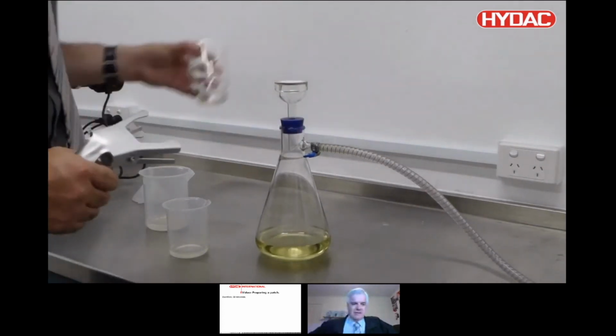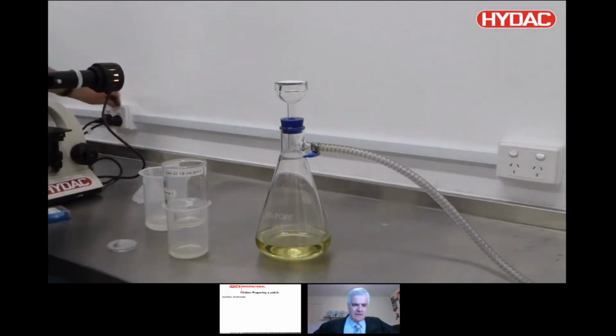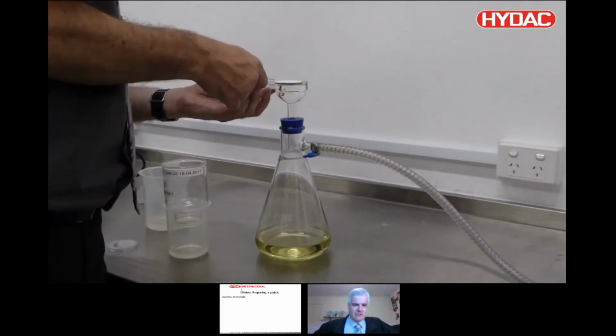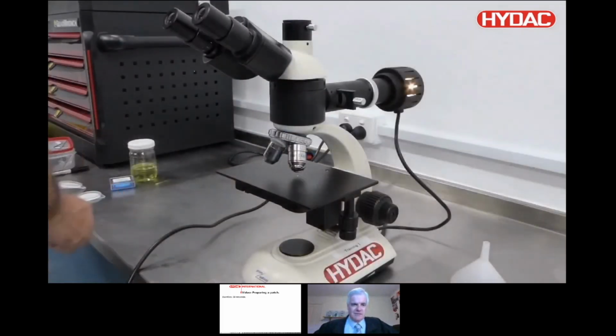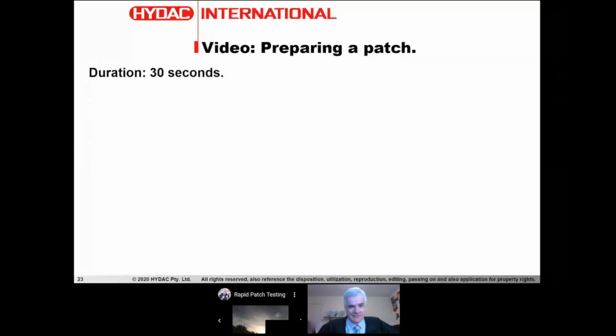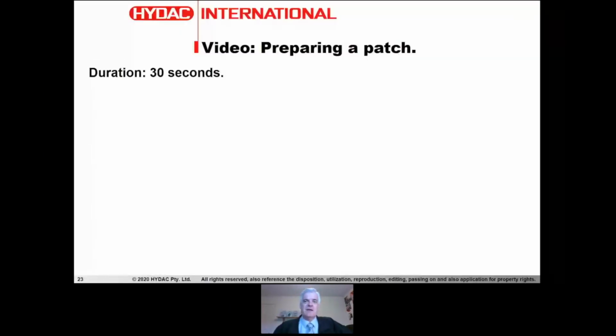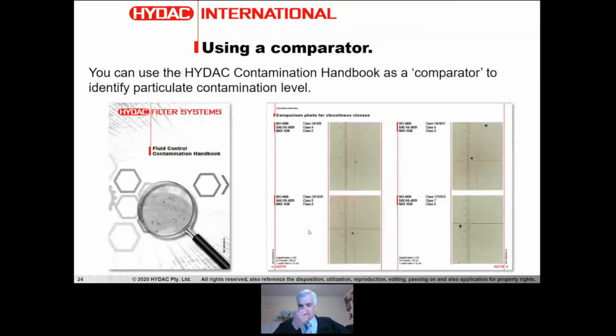Okay, so we use an ultra clean solvent here. The ultra clean solvent is filtered to a very, very fine particle size. You're evaluating 100 ml of the lubricant. You're using the clean solvent to flush it through, and then you put it under a microscope. Something happened to that video. I'm very sorry. So once you have that little patch, you put it under a microscope and you can evaluate it.